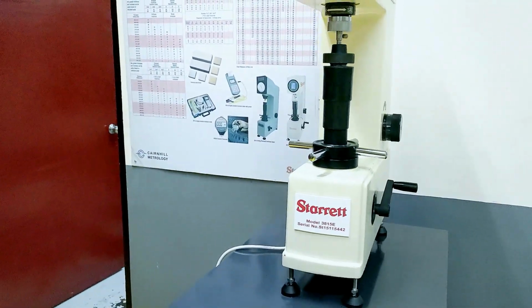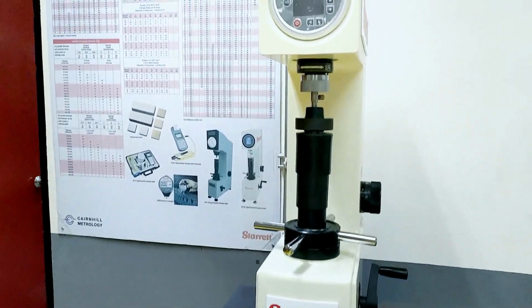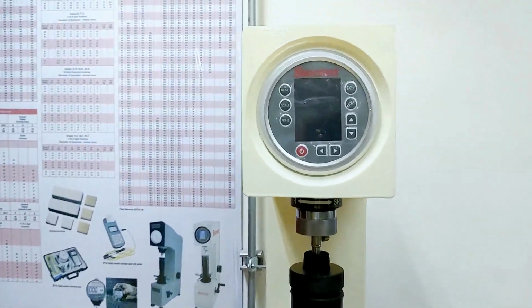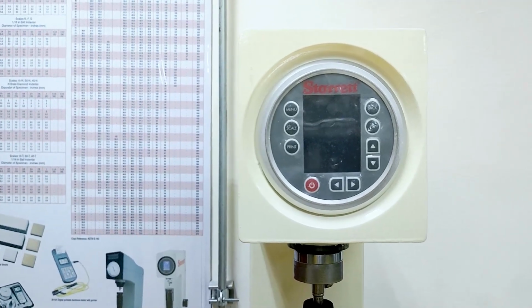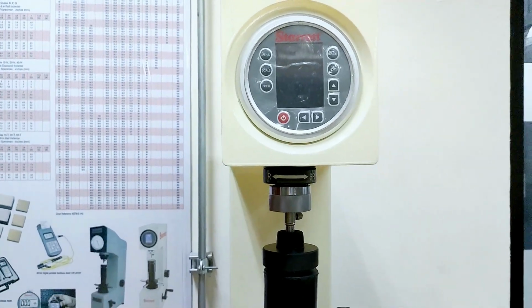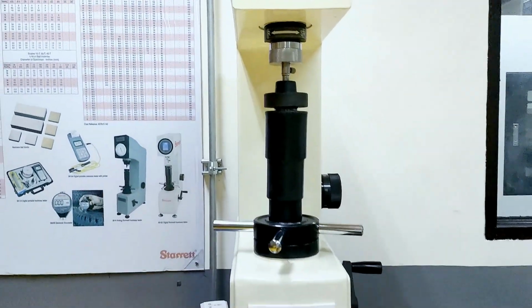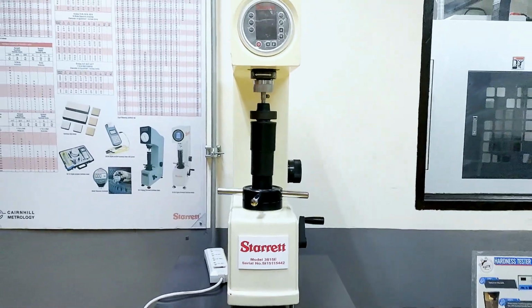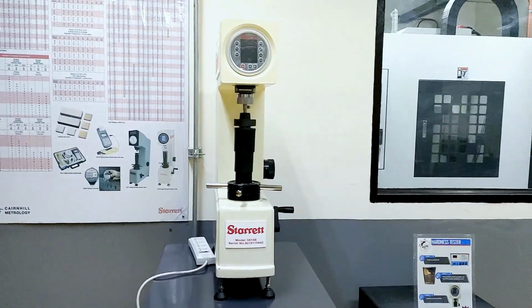The digital Rockwell hardness tester is designed to test the hardness of metals by determining the depth of penetration of an indenter under a large load, compared to the penetration made by a preload, according to the Rockwell scale.